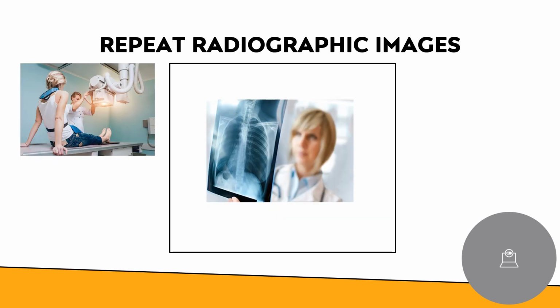So repeat radiographic images are on page 235. The DR should have reduced the number of repeats due to the fact that the majority of the repeats were due to technical factors. However, positioning errors have now risen. Some of the RTs are not positioning well enough because it's quicker to continue to redo until it is acceptable, or for those RTs that expect perfection at the expense of their patient. Many perfectionistic RTs will continue to perform repeats even when the first image was in an acceptable range to produce a diagnosis. So remember, there's a difference between optimal and diagnostic.